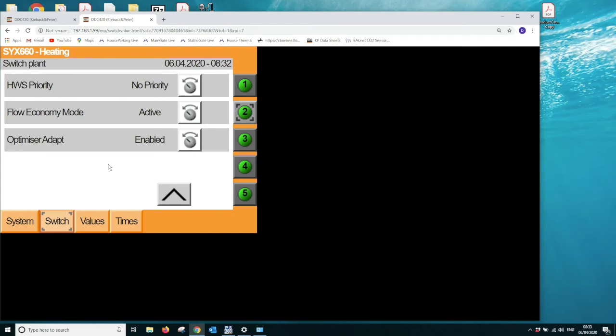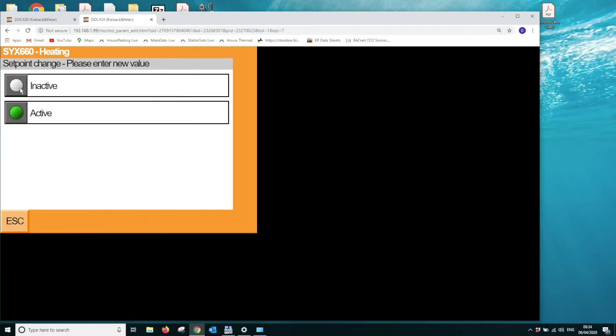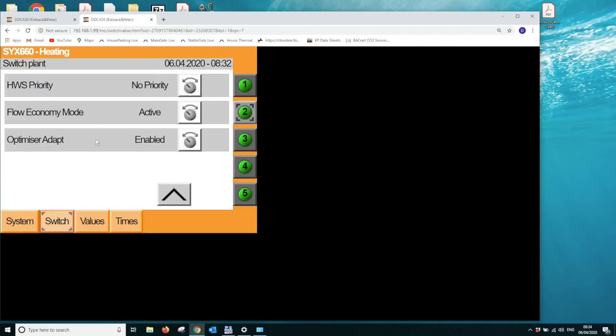Again, this can cause some conflicts in some buildings where you've got very efficient thermal mass, the building heat retention is very good and you need very little energy to heat the building up. On a mild day you could have a situation where the heating would be disabled because your calculated flow set point is very close to the room temperature. So flow eco mode will kick in. It will also kick out again should the parameters change, but equally it will come up with economy mode on the system, and that will be the reason why. Again, if it causes a problem or you're a bit unsure, you can always disable it by clicking on the inactive function.